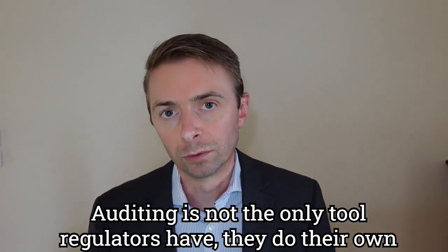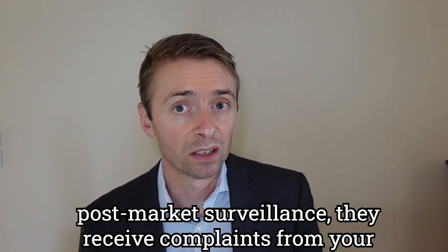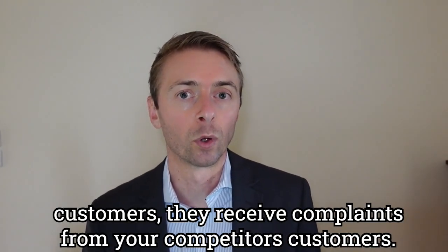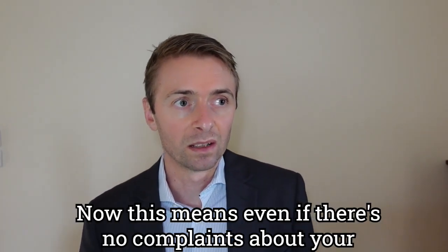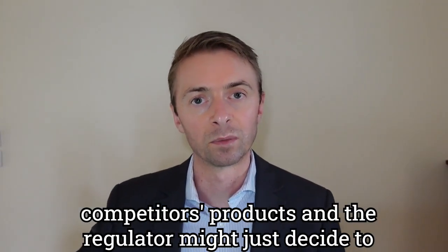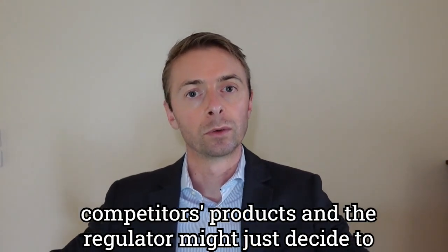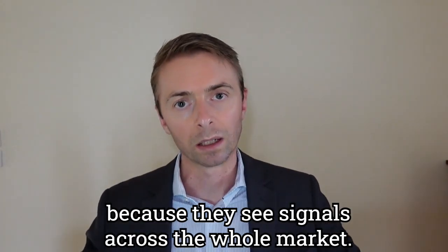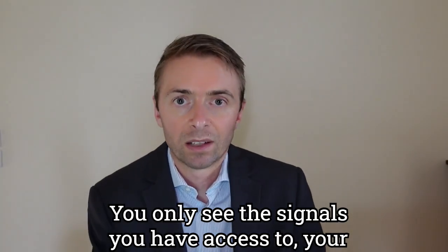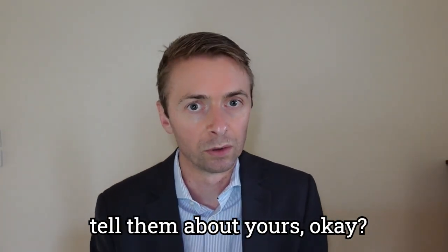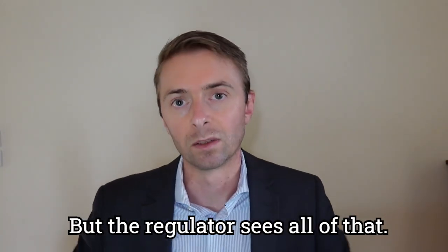Auditing is not the only tool regulators have. They do their own post-market surveillance. They receive complaints from your customers. They receive complaints from your competitors' customers. Now this means even if there's no complaints about your product, there might be a pattern of problems with your competitors' products, and the regulator might just decide to investigate you all as a group. That usually happens when regulators see a pattern, because they see signals across the whole market. You only see the signals you have access to. Your competitors don't tell you about their problems and you don't tell them about yours. Okay? But the regulator sees all of that.